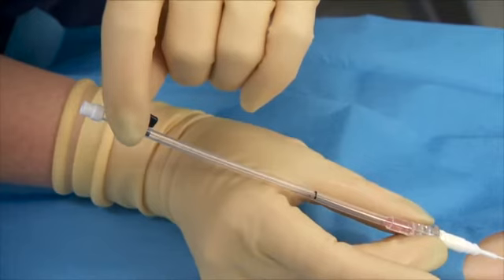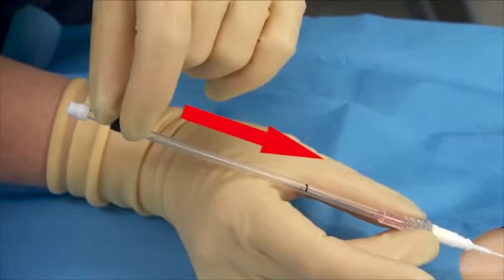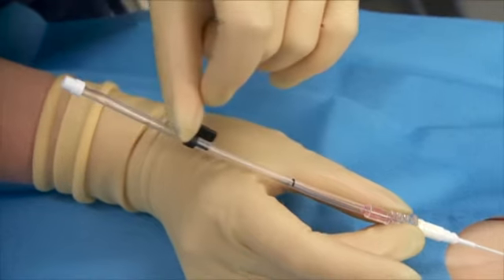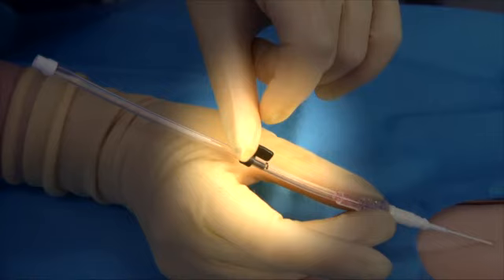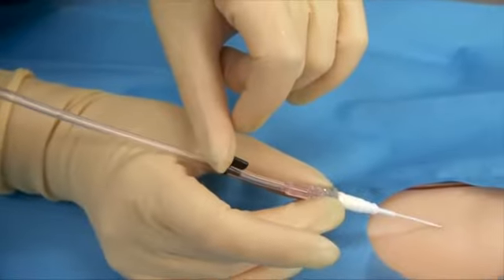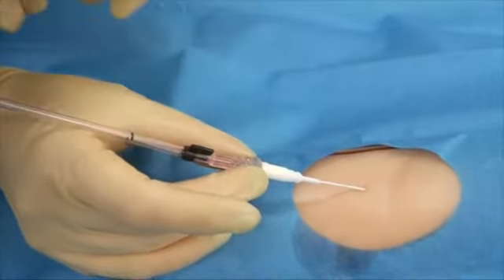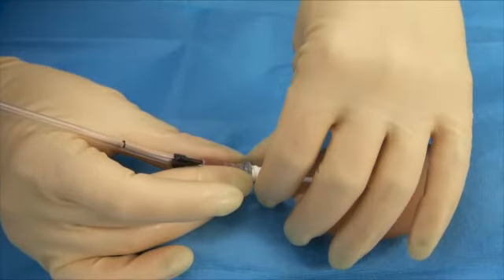Lower the placement device assembly slightly. Stabilize the position of the introducer needle and carefully attempt to advance the spring wire guide into the vessel using the spring wire guide handle. When spring wire guide handle reaches the black line on the tube, this indicates that the tip of the spring wire guide is located at needle tip. Note: if resistance is encountered during spring wire guide advancement, withdraw the entire unit and attempt a new puncture.